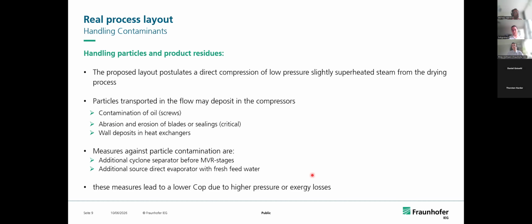If you use oil, for example, in screws, you could have contamination of the oil. But what is even more crucial and critical is that abrasion and erosion of the blades, as those are components rotating at very high speed, can damage your compressor. What you also have, which is always a problem in heat pumps but is definitely solvable and feasible, are wall deposits in heat exchangers.